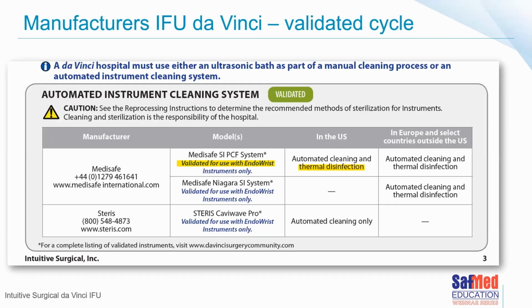This is a snippet of manufacturer's instructions for use for a da Vinci from Intuitive Surgical. The reason for sharing this is because what I want to get across is the importance of following instructions for use. All manufacturers, when they produce instruments, have to go through a validated process, and they will give you a set of guidelines on how to clean and how to process devices. And they'll stipulate what can be used in order to achieve that objective. And if something happened to you, a patient had an infection, you had a court case, the patient sues you, the first thing that anybody's going to ask you is, do you have the instructions for use, and are you following those instructions for use? A very important concept.